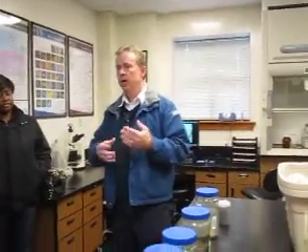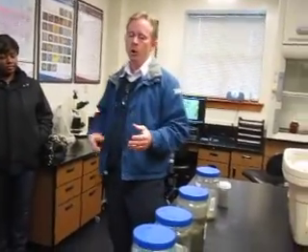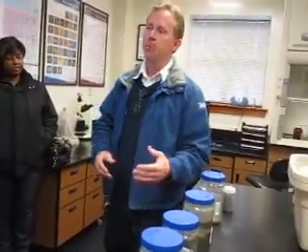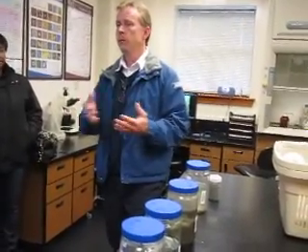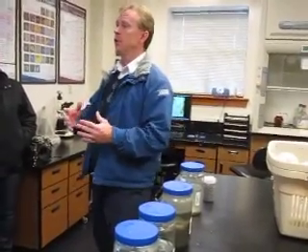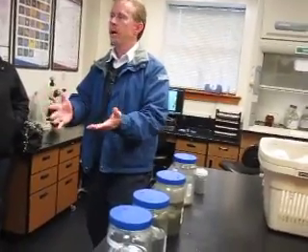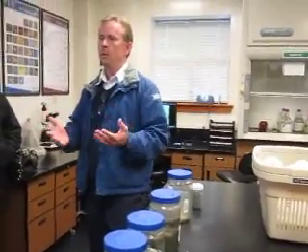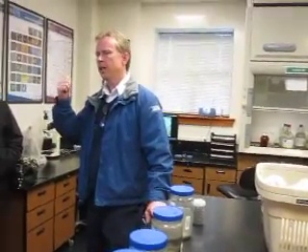It stirs things up a little more than you would like. If we had that third clarifier online, it would handle all the flow with no problems, and your water quality would be even better than what you're putting out now. But even with 2 clarifiers in service, we're well within permit limits. There's no problem, but it's just not as good as it could be if we had all 3 clarifiers in service, because you have more treatment time, more detention time. It slows everything down a little bit.